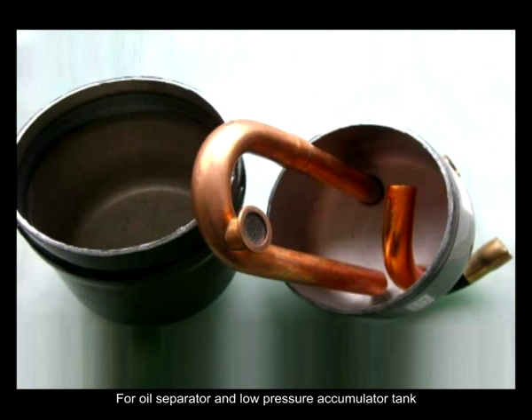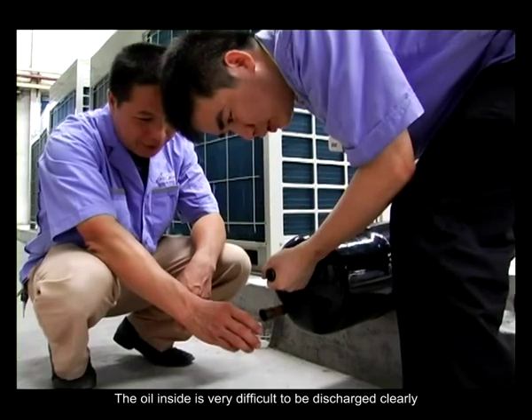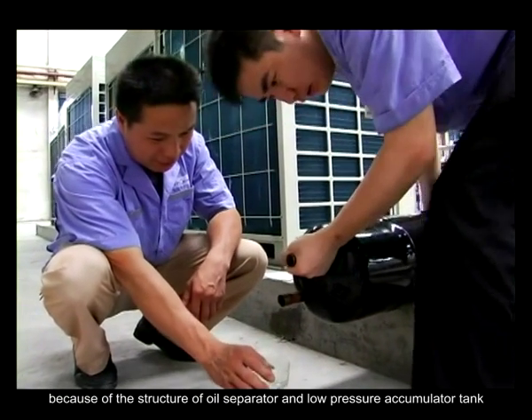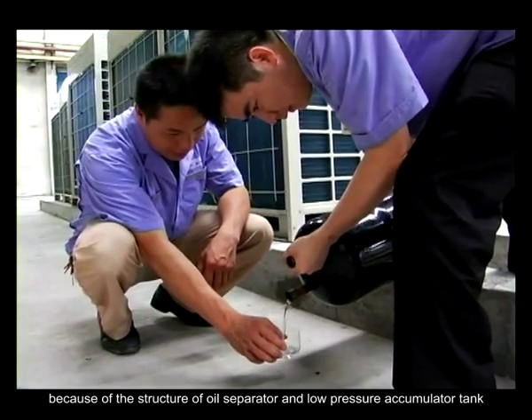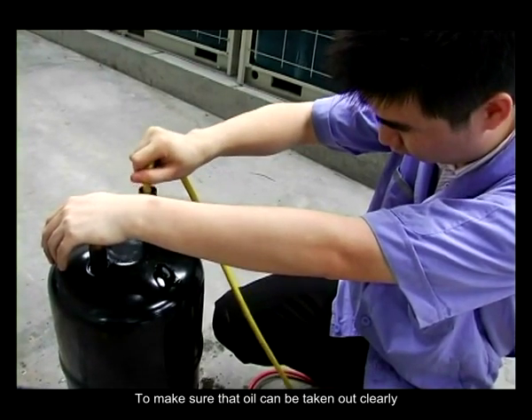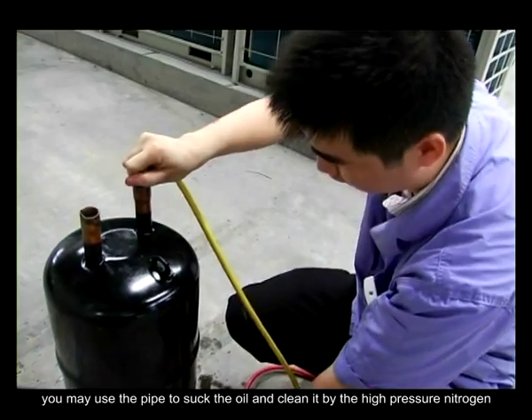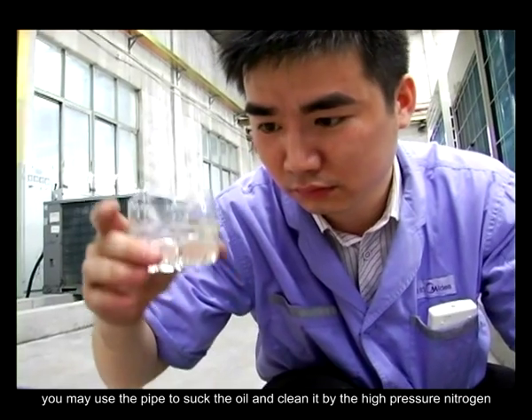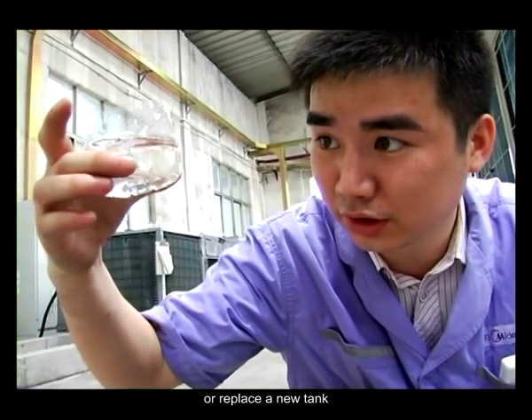For the oil separator and low pressure accumulator tank, the oil inside is very difficult to discharge completely because of their structure. To make sure the oil can be taken out clearly, you may use a pipe to suck the oil and clean it with high pressure nitrogen, or replace with a new tank.